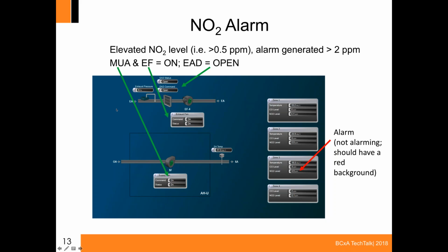So the NO2 alarm, as we tested that, at 0.5, we had the activation level of the makeup air system coming on. And then at 2.0, we did get an alarm, but you'll notice during this commissioning right here that at 4.5, we still didn't have the red background, so the building operator was not getting an alarm that this was exceeding its value. What had happened here was there had been a software upgrade to the system, and values that were input for alarm levels went back to pre-commissioned values. So that's something that we had to watch out for.